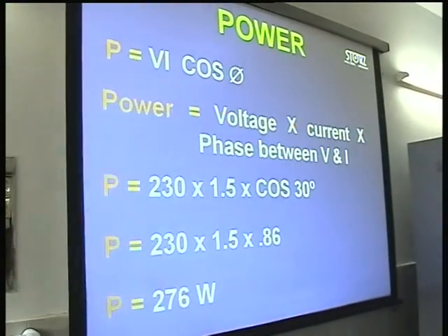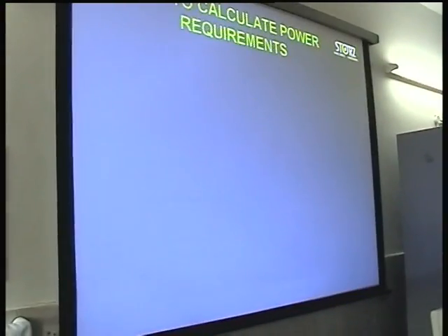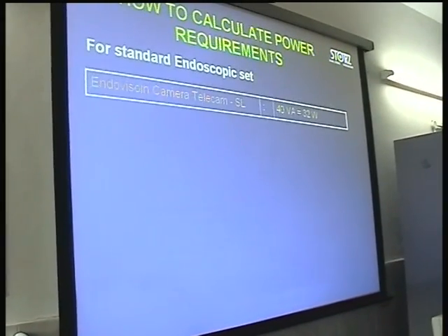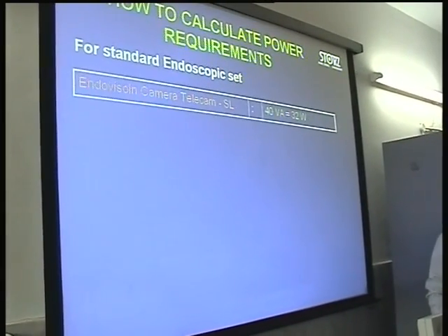Sometimes people ask, I bought your equipment, now what should be the rating of the UPS I need to install? We've learned in physics that power is voltage times current, and we have a power factor of 0.86. So whatever is the VA, you multiply by 0.86, and you can calculate the wattage power required for that particular equipment.